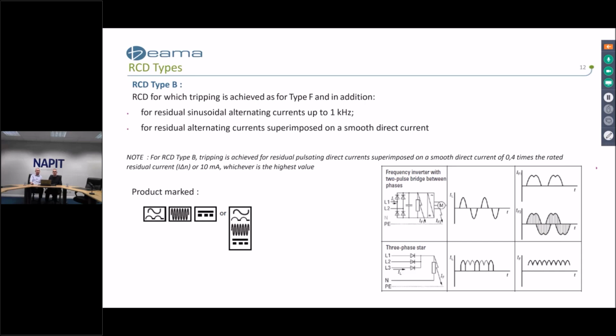And then the final RCD type to look at is Type B. Type B have been available for many years, but are becoming increasingly required due to complex electronics and loads in some modern equipment. Such electronics and loads can create complex residual currents or even smooth DC residual currents. The example waveforms given on the slide are typical of the types of residual currents that can occur. And it's very complex equipment, but with that level of switching, smoothing, and chopping, it does create very complex residual currents that AC, A, and F will not respond to.